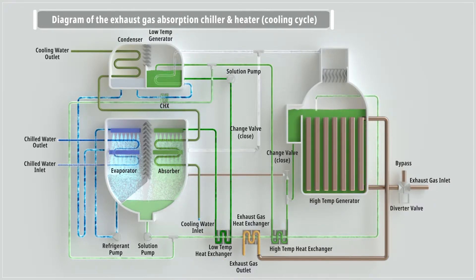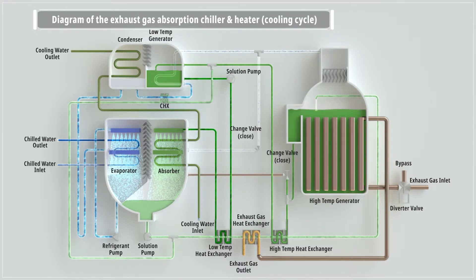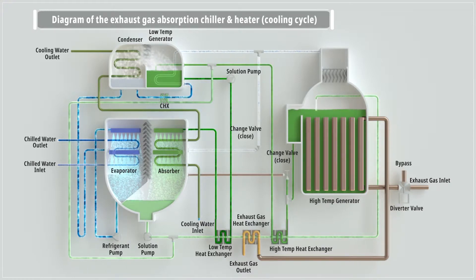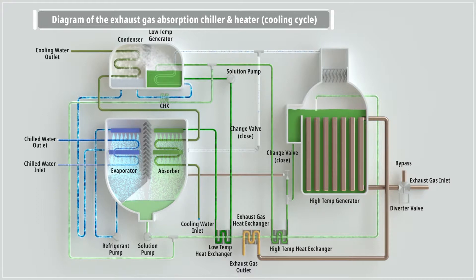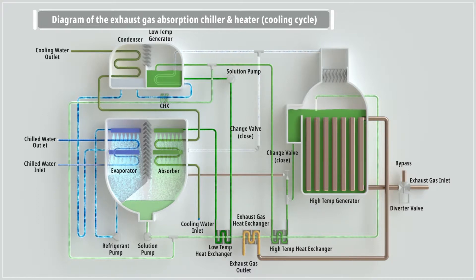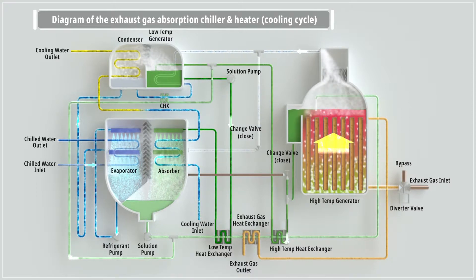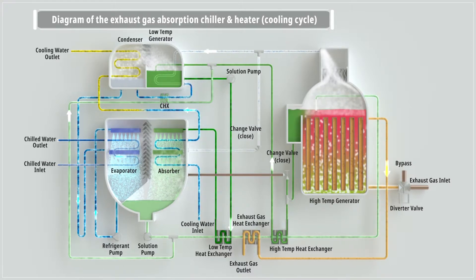Refrigerant vapor goes through the low temperature generator and condenser to be condensed and returned to the evaporator. The solution goes through the low temperature generator to release heat from the refrigerant again, becoming a concentrated solution flowing to the absorber. By repeating this cycle, the system cools down the chilled water, which is then used for cooling.